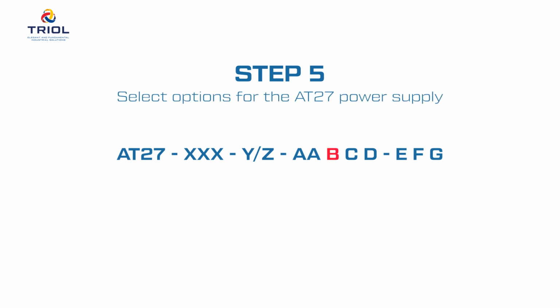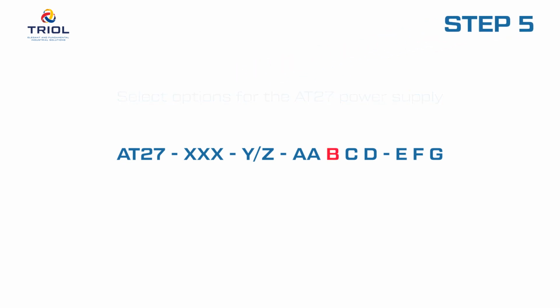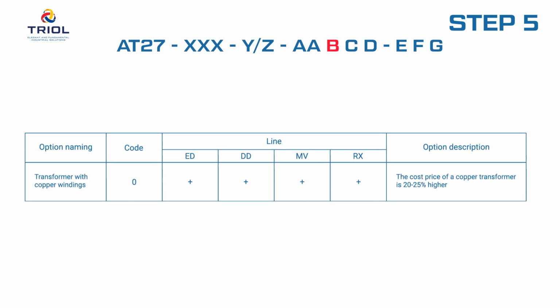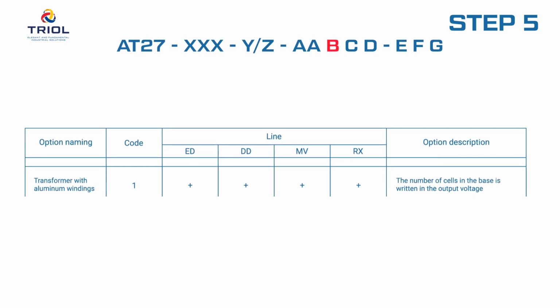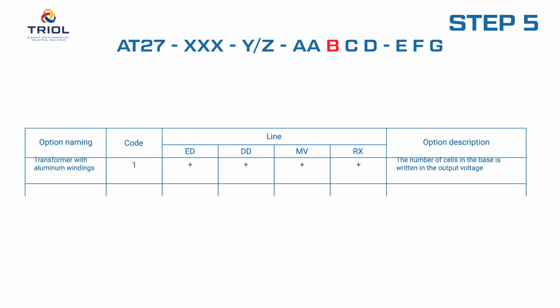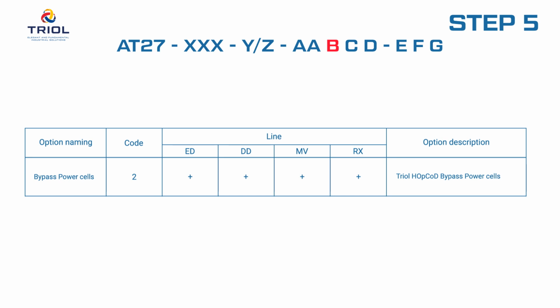The fifth step in forming the name of the AT27 is to select options for the AT27 power supply. Available options: transformer with copper windings, basic version with aluminum; bypass power cells; plus one cell per phase. Additional power circuit options are available for AT27 RX line. Built-in reactor for transferring the motor to the main and vice versa. Built-in sine filter. For ED, MV, and DD lines, the output reactor and sine filter are in separate cabinets.